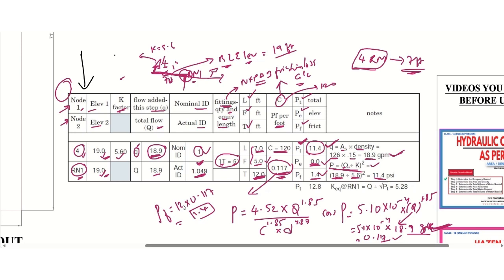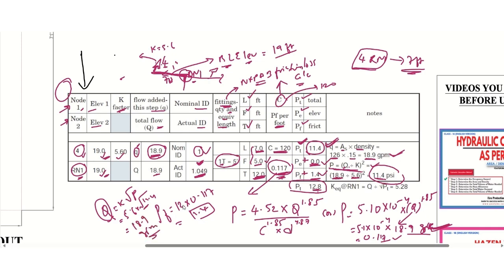Adding the initial total pressure of 11.4 psi, the elevation head of zero, and friction losses of 1.4 psi, we get a total pressure of 12.8 psi. To cross-verify: using q = k√p with k = 5.6 and p = 11.4 psi, we get 5.6 × √11.4 = 18.9 gpm — which confirms our sprinkler flow.